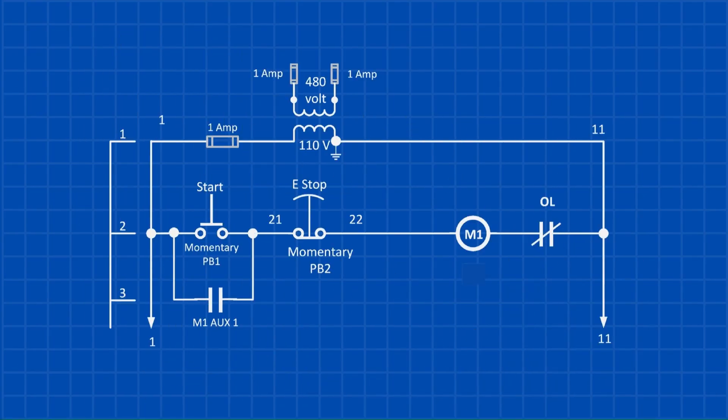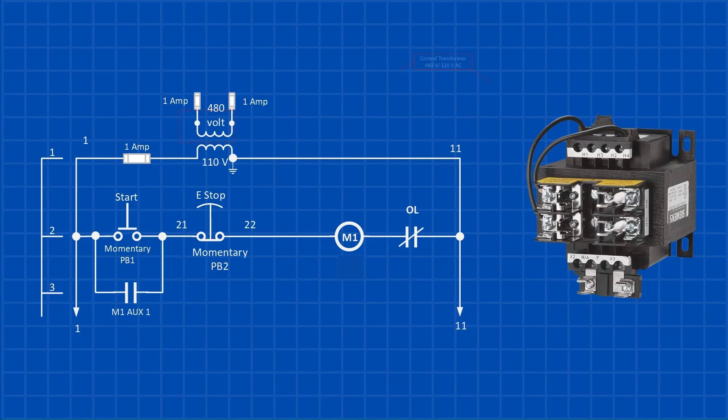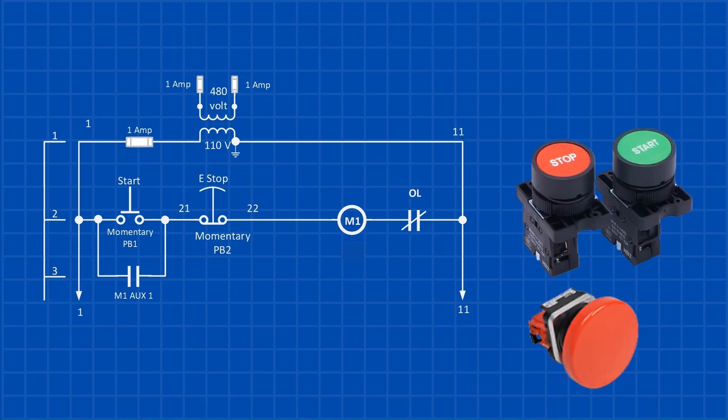Now let's take a look at the control circuit for our 30-horsepower motor. In its simplest form, the motor control circuit will look like this. The first component in our control circuit is the control transformer, which has primary and secondary fuses. It steps down the voltage from 480 volts to 120 volts AC, supplying power to the entire control circuit. The next set of components includes the momentary start and stop buttons. Notice the term momentary. This means the buttons are only active while being pressed. Once you release them, they return to their normal state.